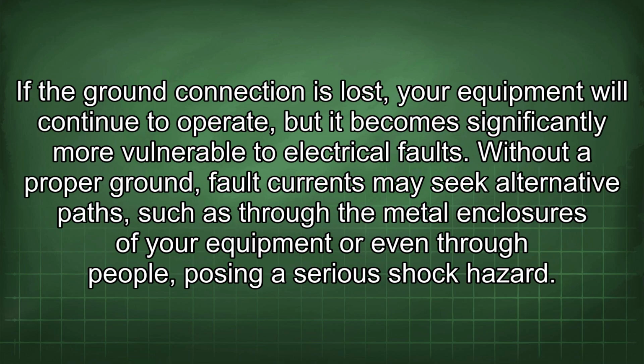If the ground connection is lost, your equipment will continue to operate, but it becomes significantly more vulnerable to electrical faults. Without a proper ground, fault currents may seek alternative paths, such as through the metal enclosures of your equipment or even through people, posing a serious shock hazard.